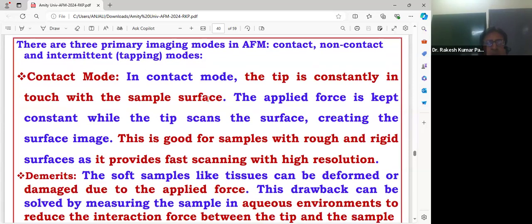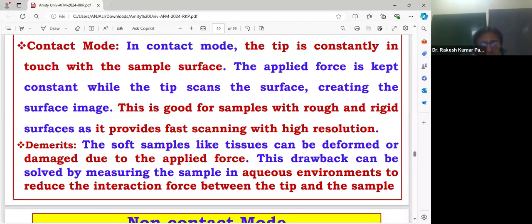Here in contact mode, as is clear from its name, the tip is constantly in touch with the sample surface. When the tip is continuously in touch with the sample surface, it is called contact mode. And here, the applied force is kept constant while the tip scans the surface, creating the surface images. Now what is the advantage of it? This mode is good for samples with rough and rigid surfaces, and it provides fast scanning with high resolution.